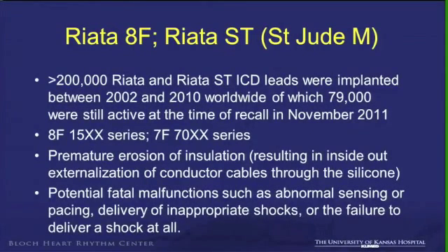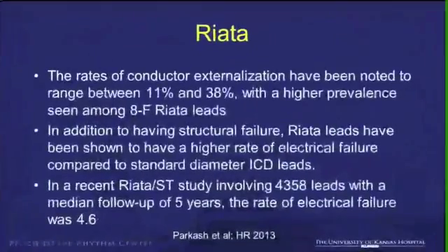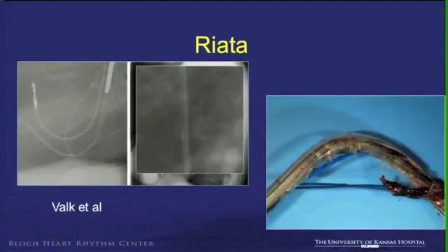The Riata has increasing frequency of fractures, with increasingly reported failures. About 200,000 Riata and Riata ST ICD leads were implanted, and they were recalled in November of 2011. The primary problem is externalization of the conductor cables. I'll show you, this is the X-ray.